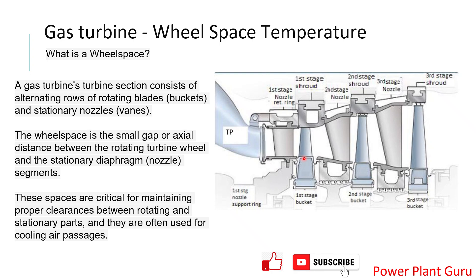Another use is during machine shutdown for inspection. When you open the machine, wheel space temperatures give an overall idea of how the different stages of the turbine sections have cooled over the entire length. Another factor is water washing, which has specific criteria: your wheel space temperature should be within certain limits so you avoid thermal shock on the materials while also allowing some temperature change so that deposits on the surface can expand, contract, and loosen up.